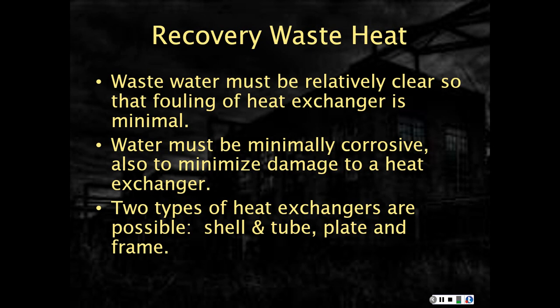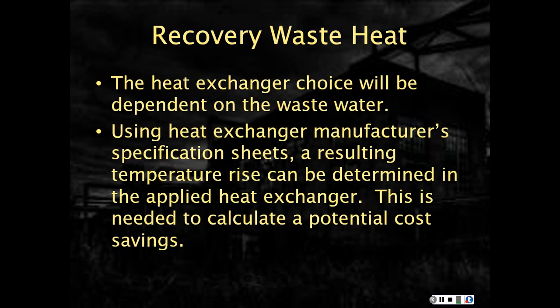you're in. You can change depending on the load over time, and you're able to get a much tighter delta T on the extraction side. So it's really up to you and your heat exchanger manufacturer to decide what's best. The heat exchanger choice will be dependent on the wastewater. Now, when you go to the heat exchanger manufacturer's specification sheets and start doing analysis, you're going to get a resulting temperature rise that can be applied to this particular situation and a particular heat exchanger.